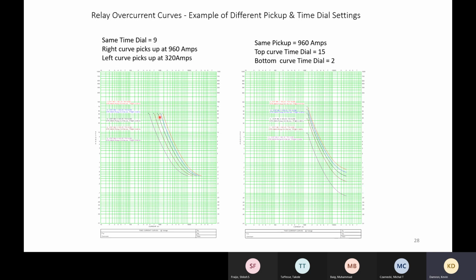So you can see by adjusting the pickup, I can move the curve left or right. For the time dial, again, here we have the same pickup, but we go from a time dial 2 to a time dial 15. The 2's here, the 15's up here. So with the time dial, I move the curve up and down. With pickup, I move the curve left and right.